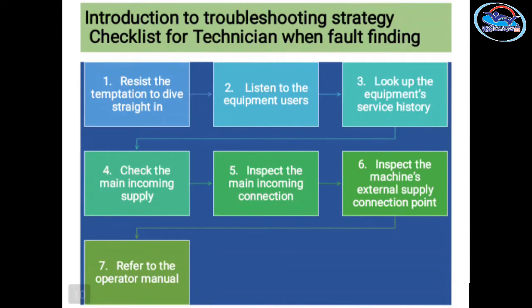For the fourth step, check the main incoming supply. Inspect the main incoming supply connections, including the plug, connectors, and mains incoming lead. Inspect the machine's external supply connection point. You can check the electrical section and connectors for any issues.